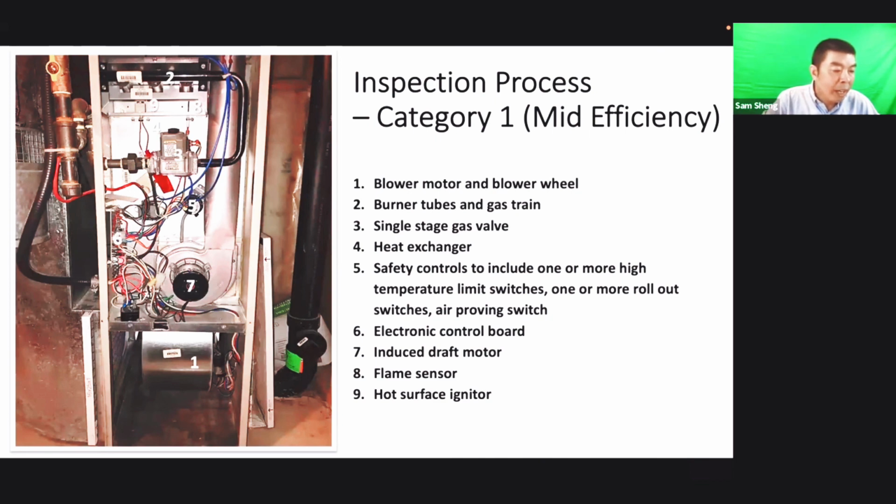If you see white debris, note it in the report and let the customer know that this igniter may need to be changed to a new one.